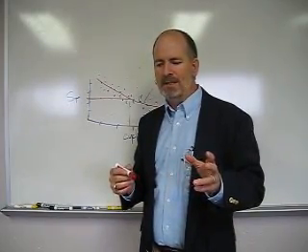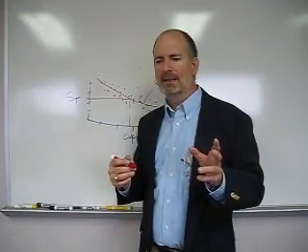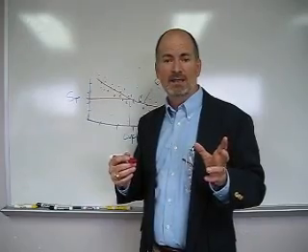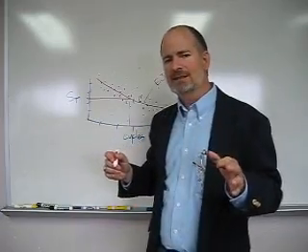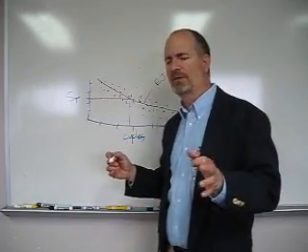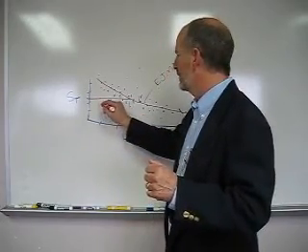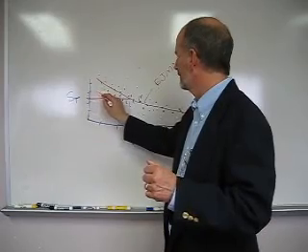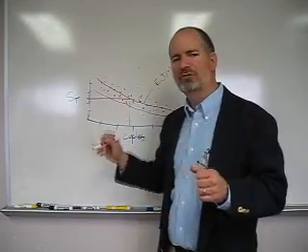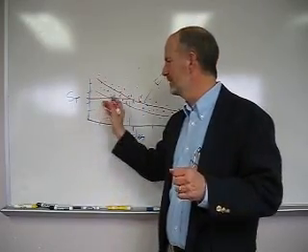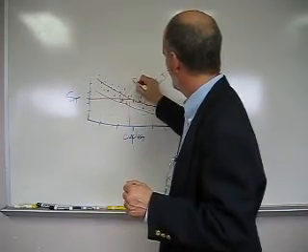So here's what the ASME, there was an ASME B31.3 Committee and then there was a Section 8 Committee, Appendix 26 Committee. The B31.3 guys said, I don't think we want a best fit curve. I think we want to be a little bit more conservative than that, and we want to do kind of a lower bound curve that pretty much captures everything. We want this curve to be really safe, and that's going to be our curve. That's the B31.3, it's got more factors of safety in it.